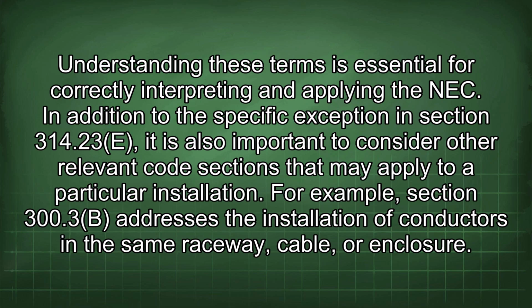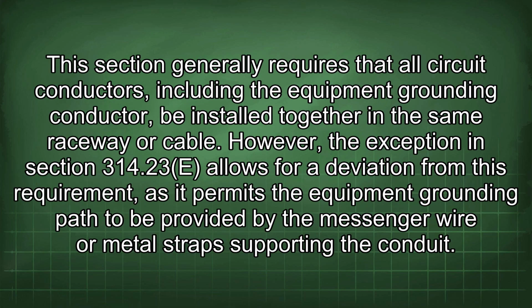In addition to the specific exception in section 314.23(E), it is also important to consider other relevant code sections that may apply to a particular installation. For example, section 300.3(B) addresses the installation of conductors in the same raceway, cable, or enclosure. This section generally requires that all circuit conductors, including the equipment grounding conductor, be installed together in the same raceway or cable. However, the exception in section 314.23(E) allows for a deviation from this requirement, as it permits the equipment grounding path to be provided by the messenger wire or metal strap supporting the conduit.